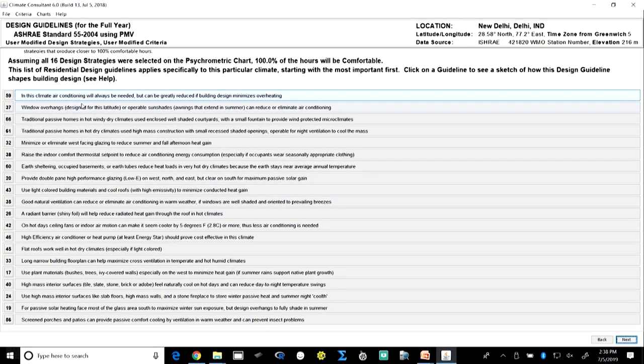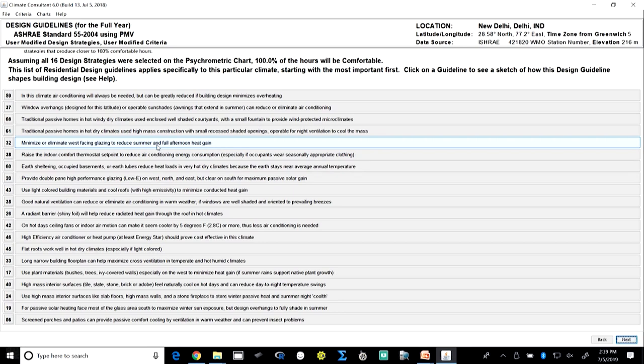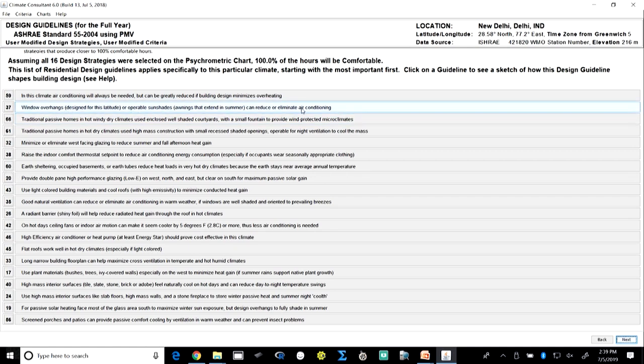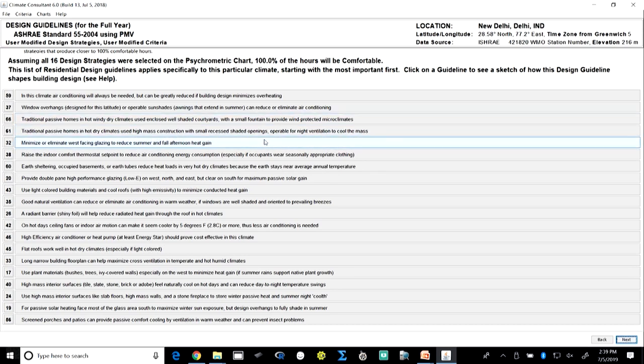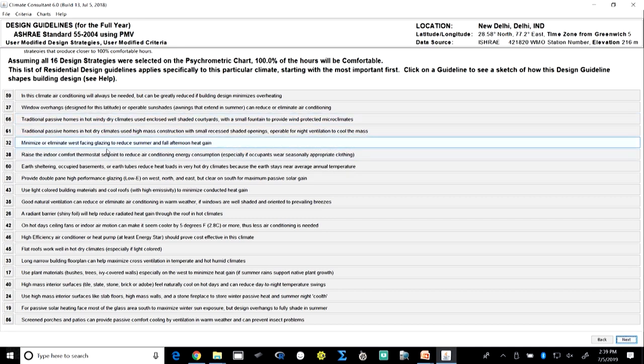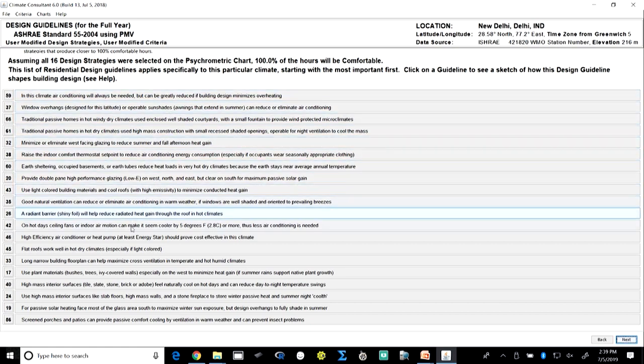We can also see the design guidelines from the software for how building design should be done to achieve thermal comfort. It says window overhangs or operable sun shades should be provided to reduce the need for air conditioning. Building construction should have small recessed shaded openings — smaller windows are preferred — which are operable for night ventilation to cool the mass. It also recommends minimization or elimination of west-facing glazing to reduce summer and fall afternoon heat gain. Each of these strategies further helps increase comfortable hours.